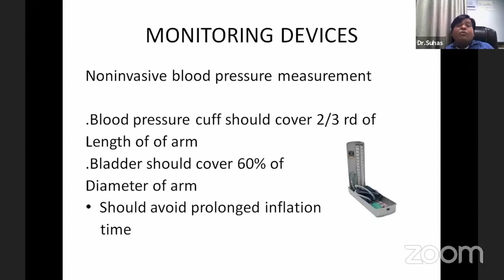So how to choose a proper size blood pressure cuff? The cuff should cover 2/3 of the length of the arm, and the bladder should cover at least 60% of the diameter of the arm. That will be the appropriate size. Now newer cuffs are coming where the mid-arm circumference is mentioned, so you can directly measure the mid-arm circumference and choose the cuff. But if the mid-arm circumference is not mentioned on the cuff, you have to check this: the cuff should cover 2/3 of the length of the arm and the bladder should cover 60% of the diameter. And you should avoid prolonged inflation, because prolonged inflation will stop the blood supply to that extremity. There can be fatigue and cyanosis, because children are more prone to this if you do prolonged inflation.